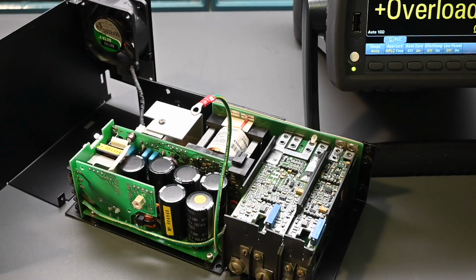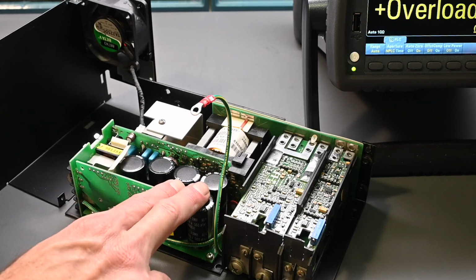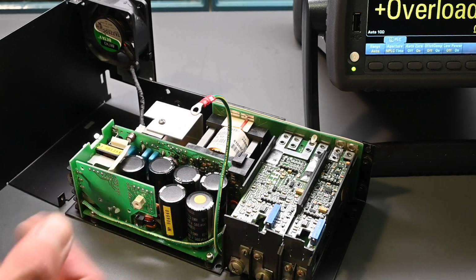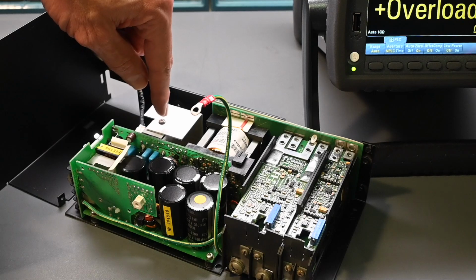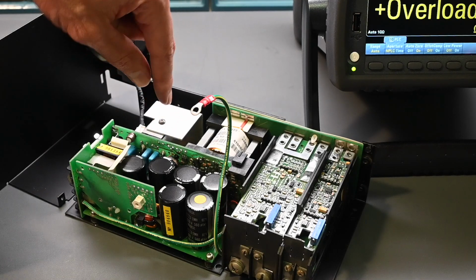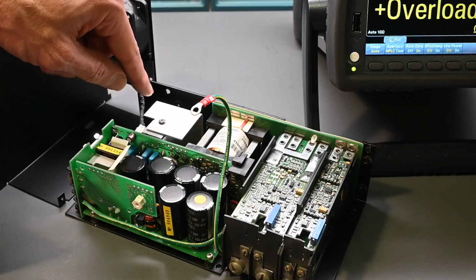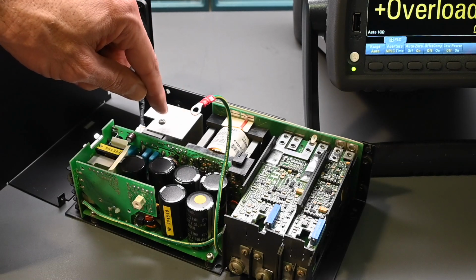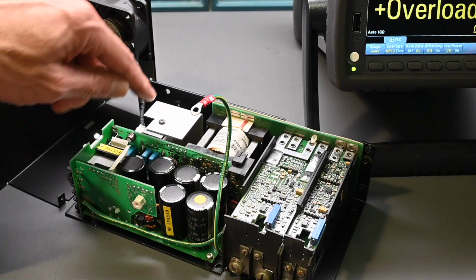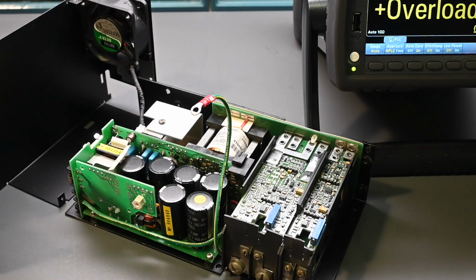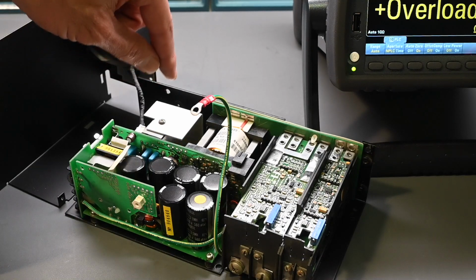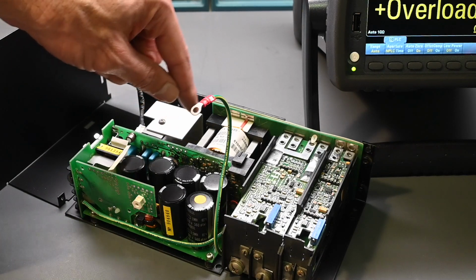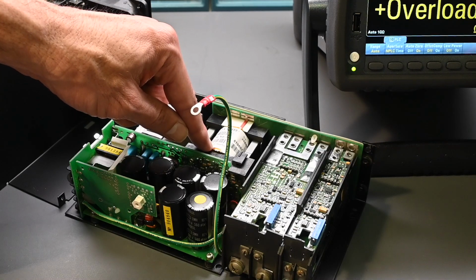That bridge rectifier is configured in different ways depending on the high or low voltage setting with this link over here. At that point you have high voltage DC, and that high voltage DC is switched at about 100 kilohertz by probably a power FET or MOSFET on this heatsink. There's actually two of them, it looks like there's another one down below. You have to be careful because this heatsink could possibly be electrically live when in operation, so you never want to touch an exposed heatsink like this. You'd certainly want to measure it first and see if there's any voltage potential on it.